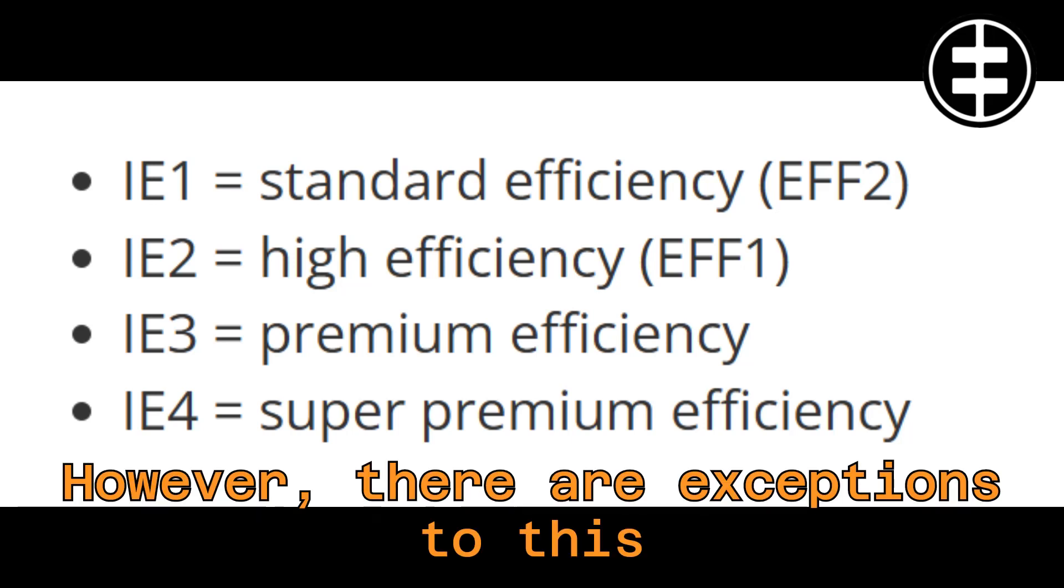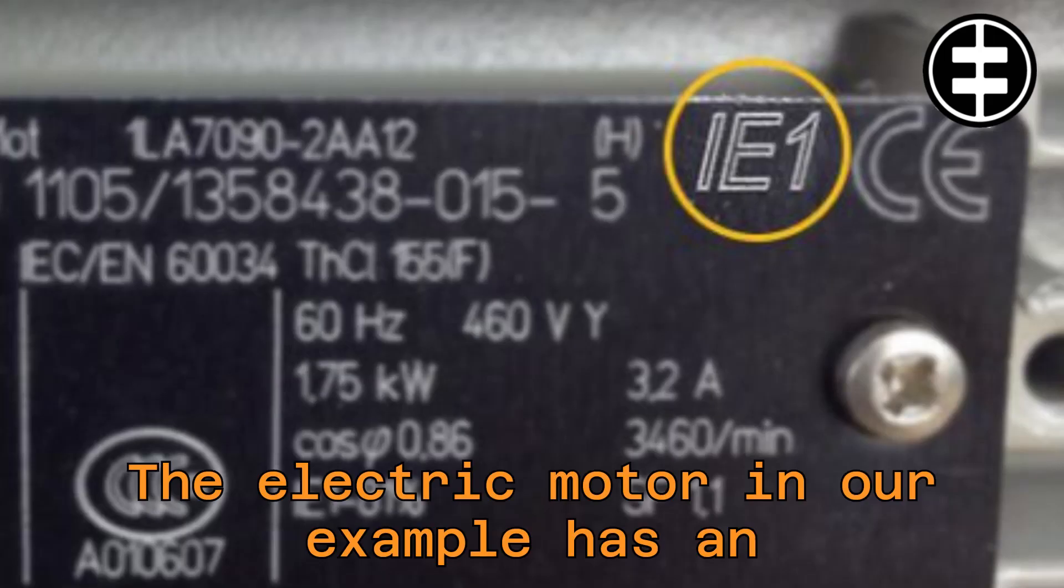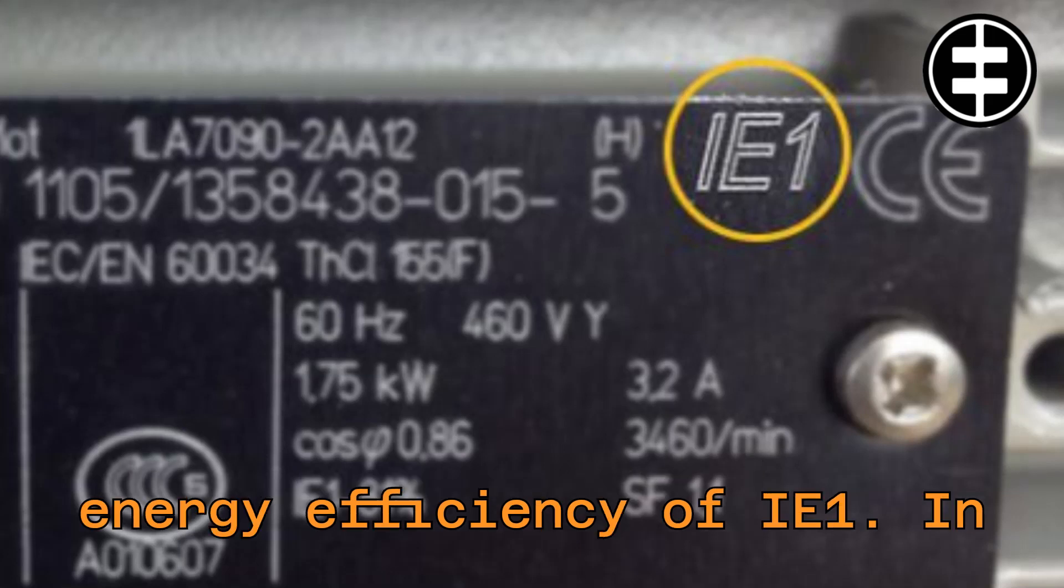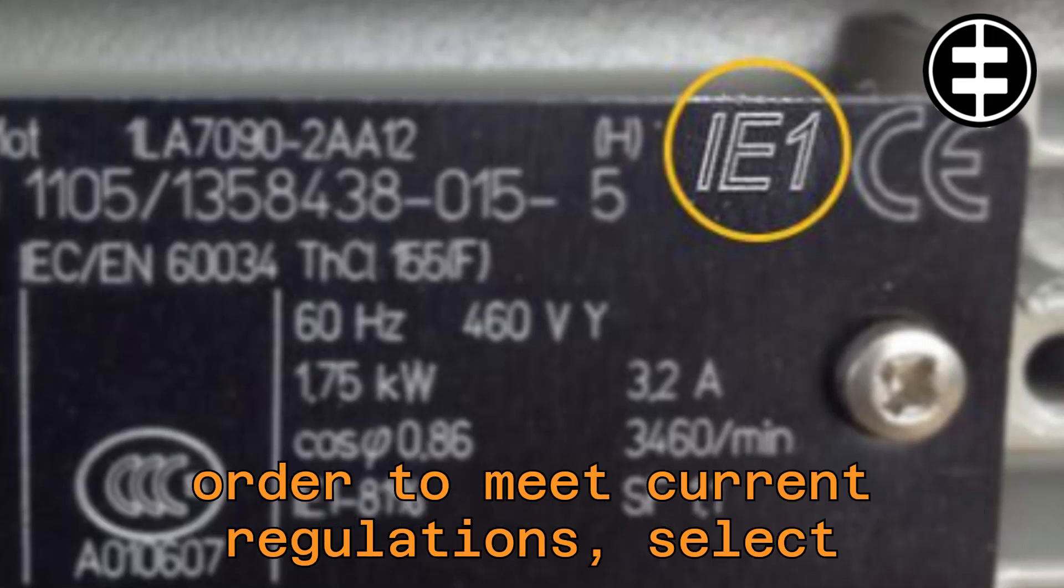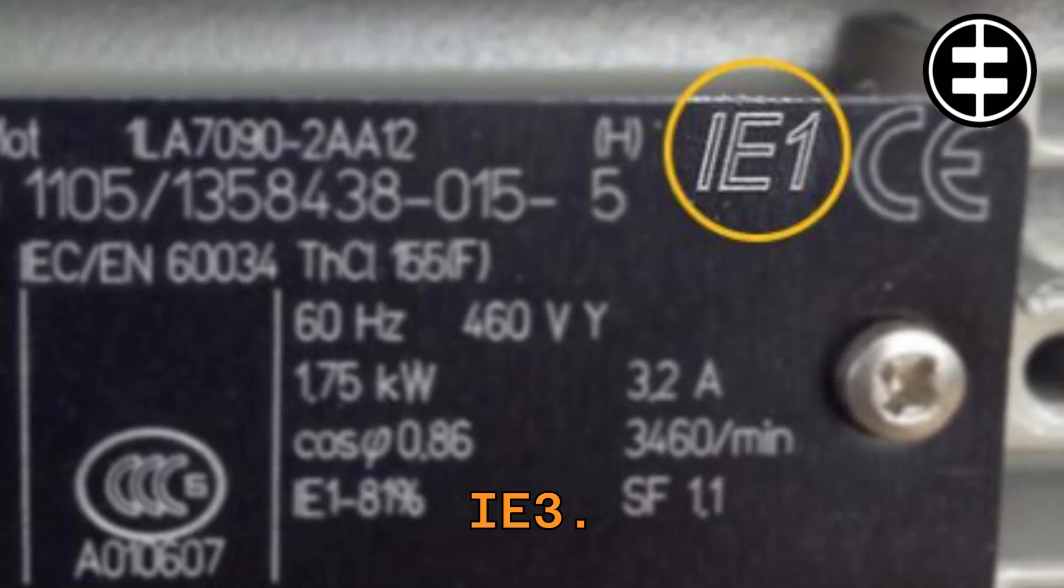However, there are exceptions to this rule. The electric motor in our example has an energy efficiency of IE1. In order to meet current regulations, select IE3.